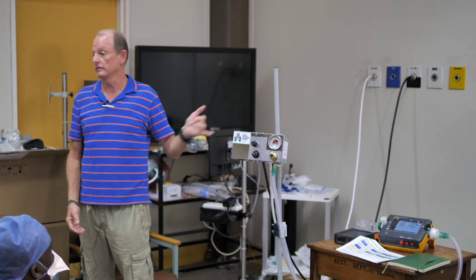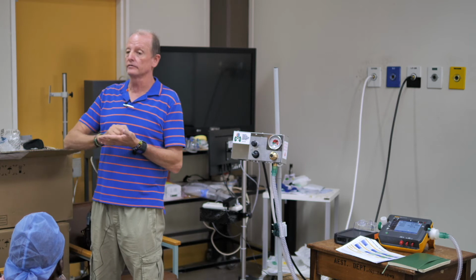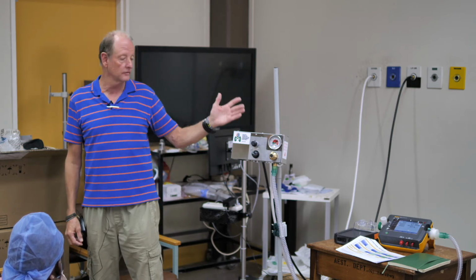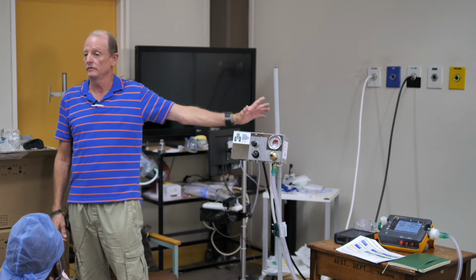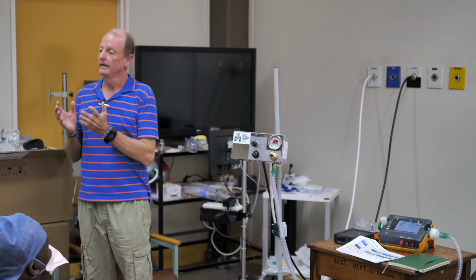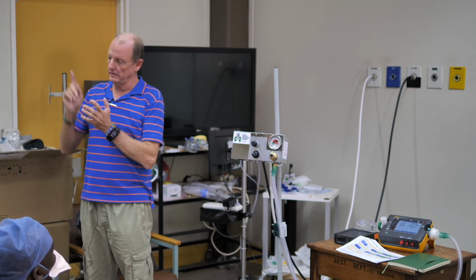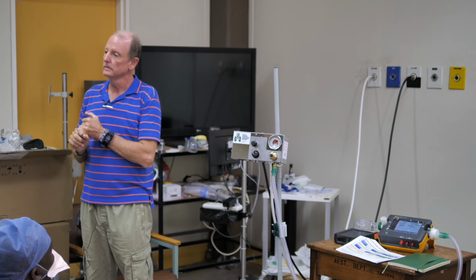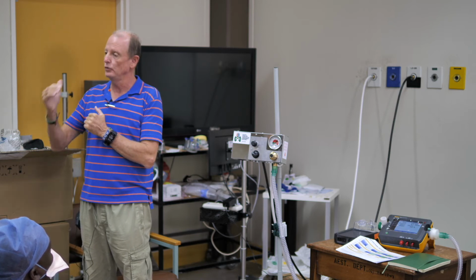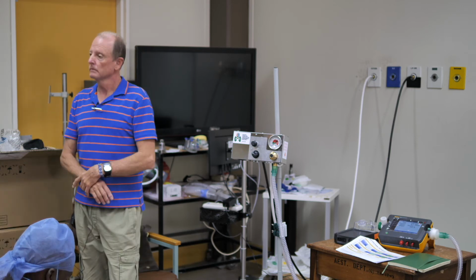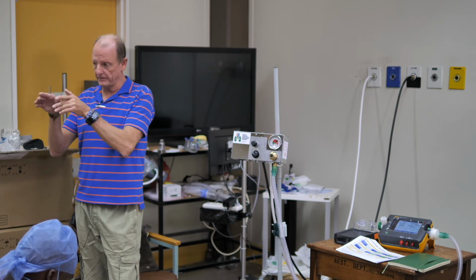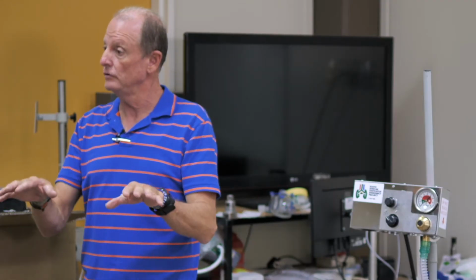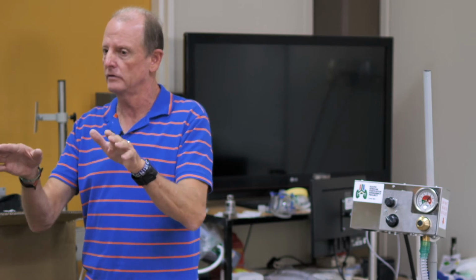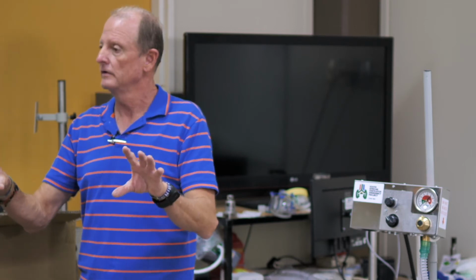Every single one of these units, probably in the box you'll see my signature, because every single one of those units was tested. 2,000 units were tested. They will have records at the factory, and I can find out exactly where it was sent. Just another thing for you to be aware of is it went to the central stores, the HTU unit, the Health Technology Unit. I don't know whether you communicate with them. Everything goes via them, distributed to the hospitals.